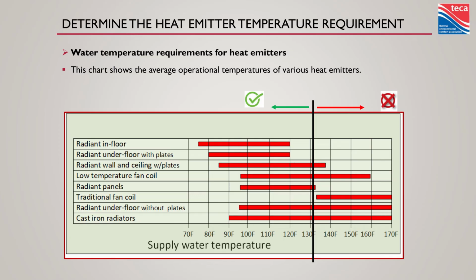Great application. We've got our radiant walls and ceilings. Great way to increase some surface area in a space if you're limited by cabinets or stairs or other things in a room. Got radiant panels, cast iron radiators, but some of these things need some pretty hot temperatures. So let's just draw a line. Nothing to the right is going to be a good fit. Everything to the left, going to be a good fit. Try to size it for the lowest temperature possible.